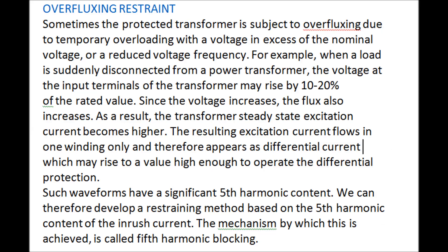Over-fluxing restraint: the protected transformer may be subject to over-fluxing due to temporary overloading with voltage in excess of the nominal, or a reduced frequency. For example, when a load is suddenly disconnected, the voltage at the input terminal may rise by 10–20% of the rated value. Since voltage increases, flux also increases, causing the transformer's steady-state excitation current to become higher. This excitation current flows in one winding only and therefore appears as a differential current, which may be high enough to operate the relay. Such waveforms have a significant fifth harmonic content, and a restraining method based on the fifth harmonic content is used — called fifth harmonic blocking.